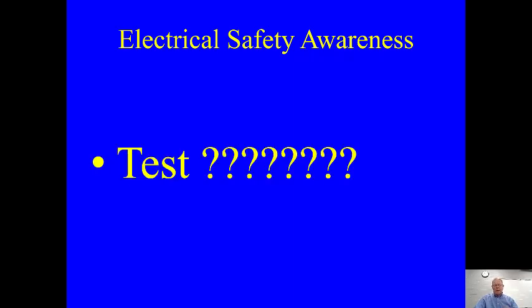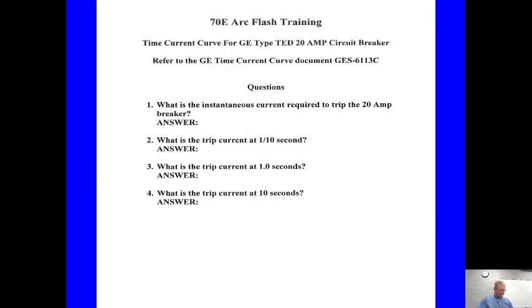So normally when I give this to electricians, I give them a test and talk about circuit breakers. If you take a circuit breaker - this happens to be one just like out of your house - I'll ask if they've ever reset a breaker. Maybe you have, and that thing trips once a day, maybe at 2 o'clock in the afternoon on a summer day when the temperature's 95 plus, that breaker trips. Well, breakers trip on heat, and they don't care where the heat comes from.